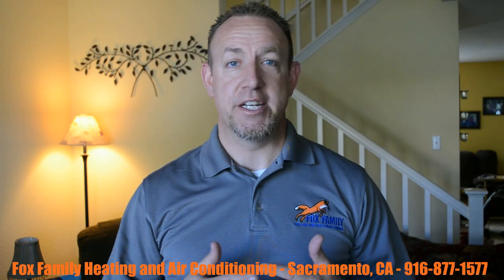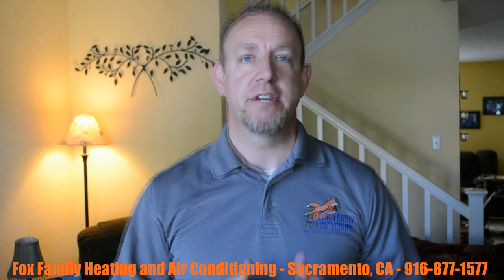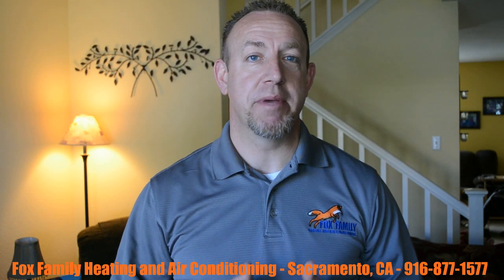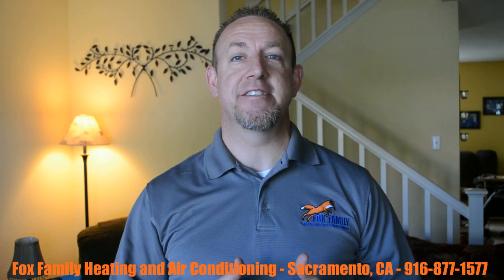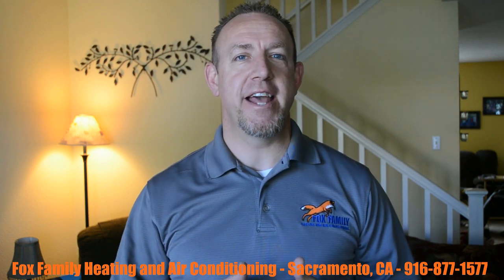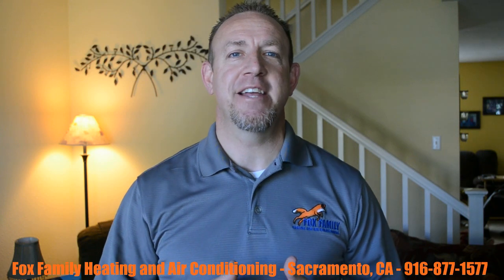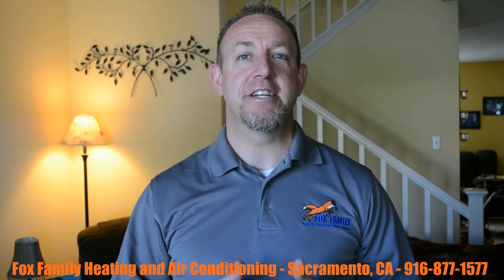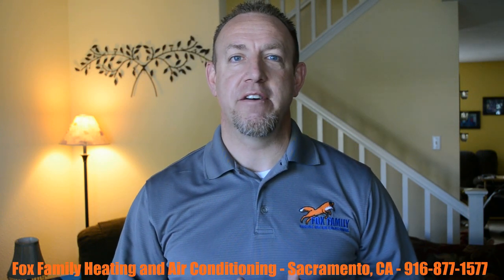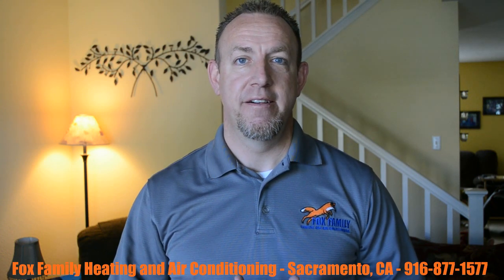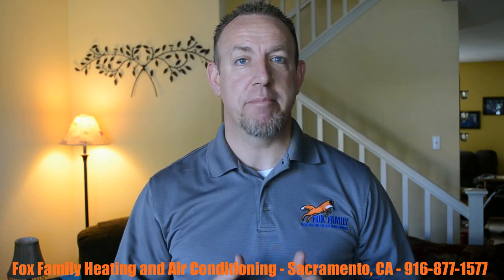A lot of times the contactor or the capacitor has gone bad and that might need to be changed. I would say that 85% of my calls in the beginning of summer are due to a bad capacitor. If your capacitor or contactor are damaged, the AC will need to be repaired by either you or a local certified HVAC technician like Fox Family Heating and Air Conditioning. I must stress though, if you're going to do this repair yourself, there are serious problems that can happen if you don't make the repair correctly. There's high voltage running through the system with other very expensive parts that can be damaged.